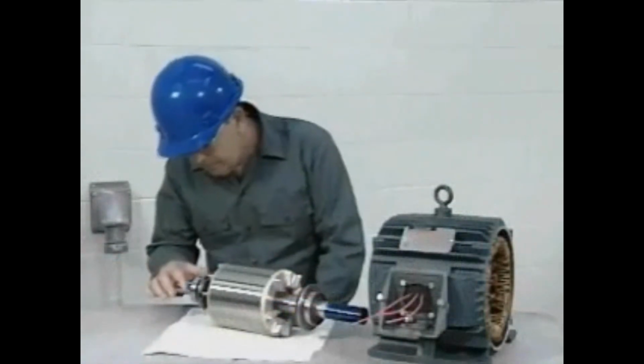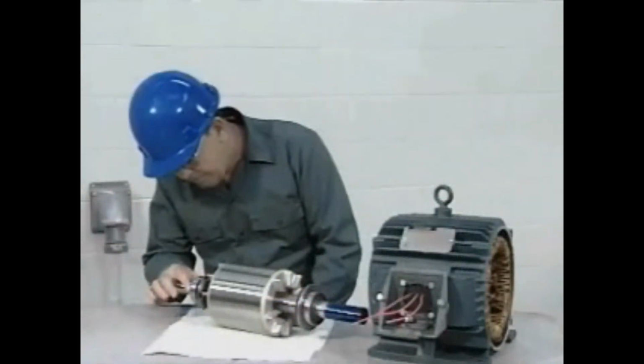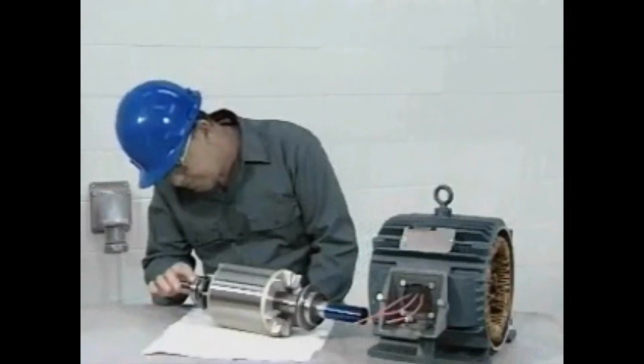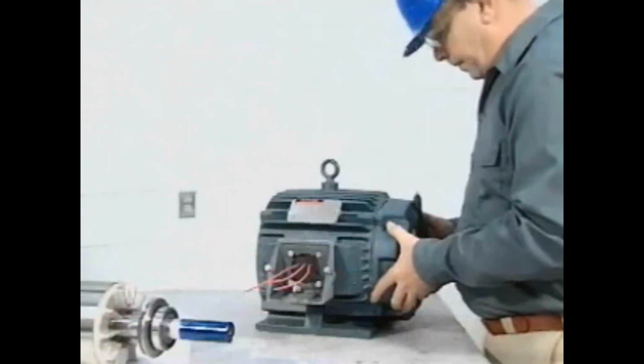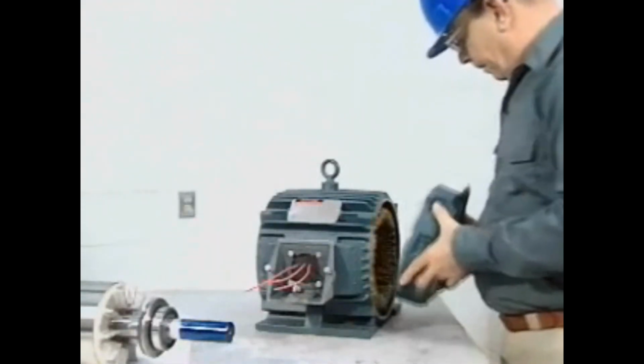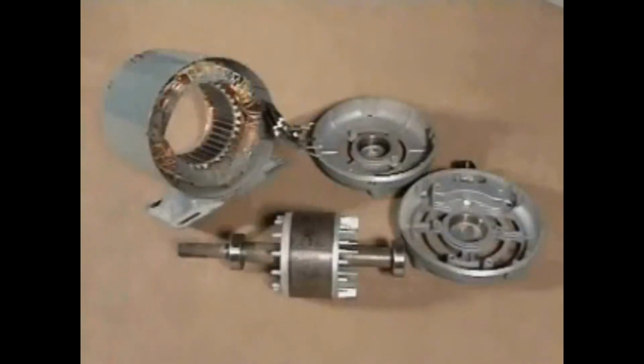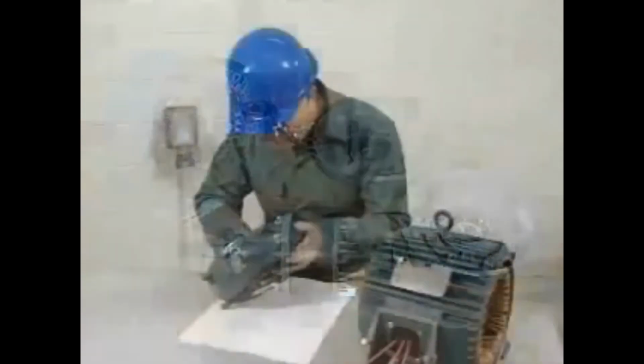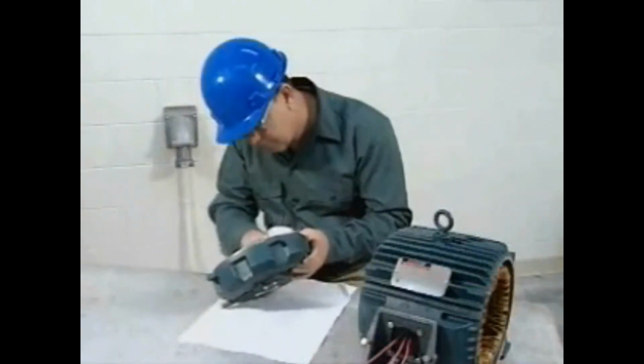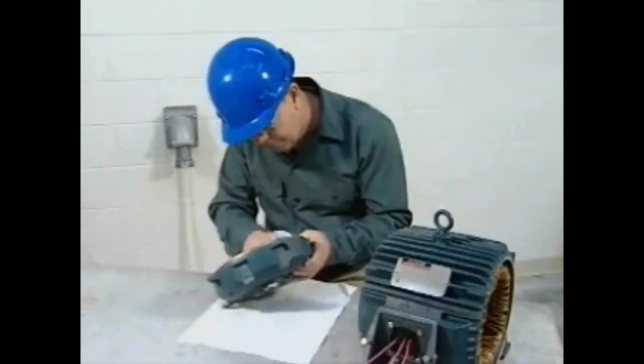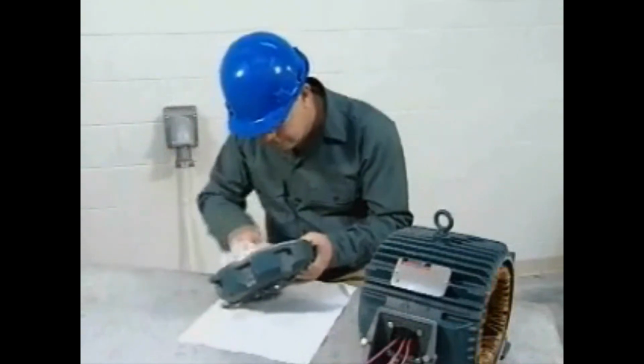Inspect the bearings according to the manufacturer's instructions. Replace the bearings as necessary. Remove the other end bell. Select Next to continue. Once you have disassembled your motor, you're ready to inspect and clean the parts. Wipe the end bells with a soft, lint-free cloth. Inspect them for cracks and other signs of damage.